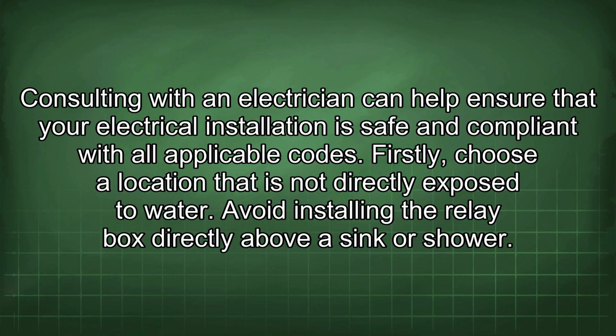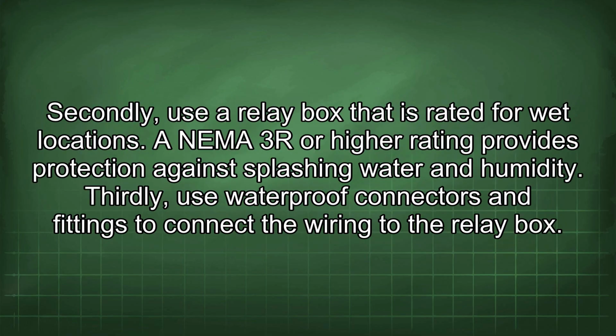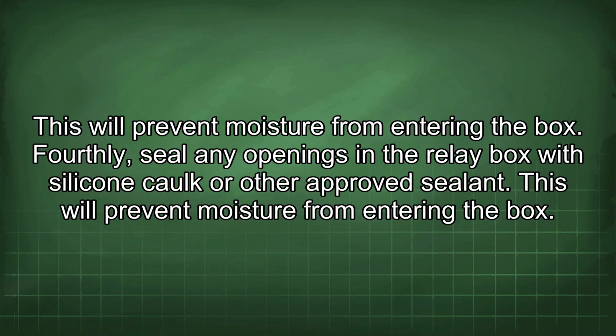Firstly, choose a location that is not directly exposed to water. Avoid installing the relay box directly above a sink or shower. Secondly, use a relay box that is rated for wet locations. An NEMA 3R or higher rating provides protection against splashing water and humidity. Thirdly, use waterproof connectors and fittings to connect the wiring to the relay box. This will prevent moisture from entering the box. Fourthly, seal any openings in the relay box with silicone caulk or other approved sealant. This will prevent moisture from entering the box.